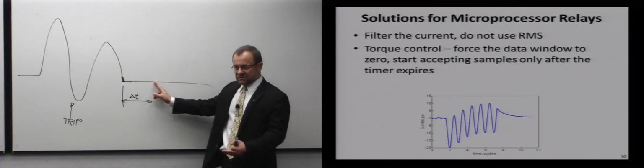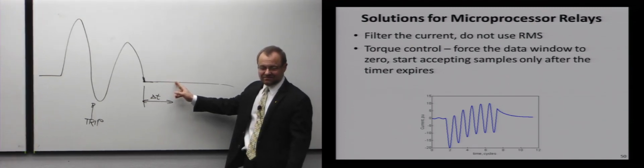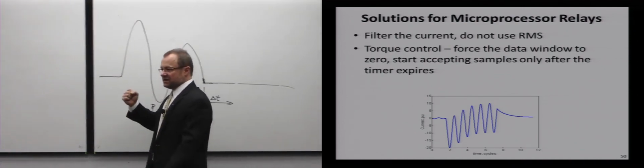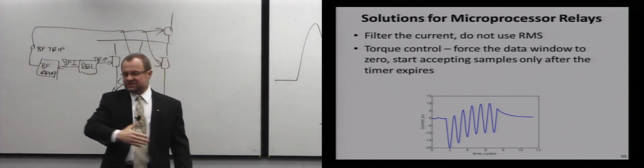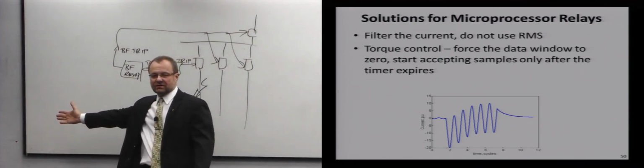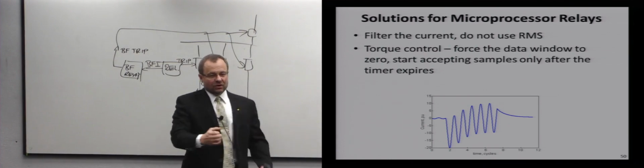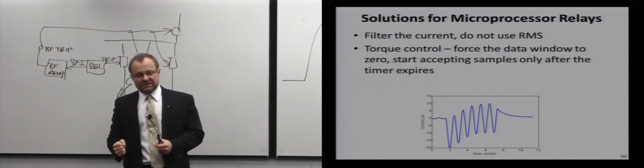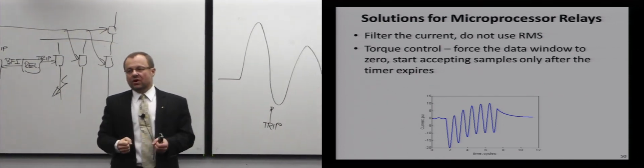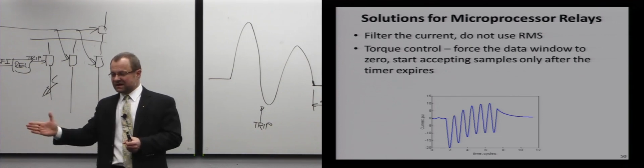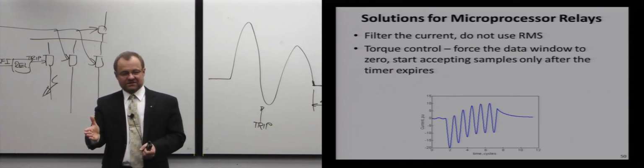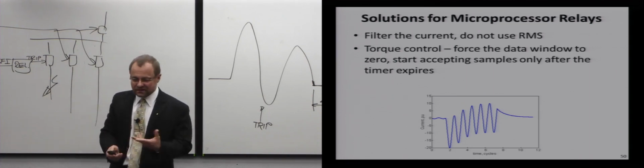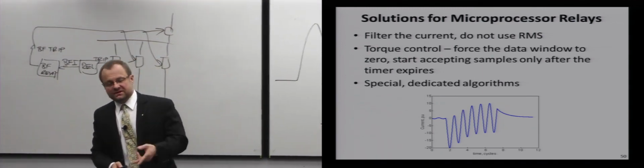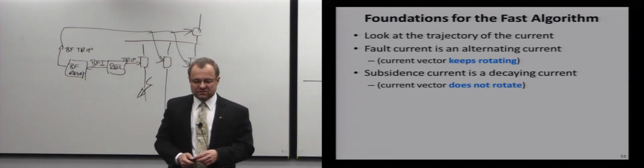So when my timer expired, say up to here, I start running that estimator and I say take a sample and see and run it through a Fourier. So if the current is gone, I will fill my window with zeros and the output I'm getting is zeros, right? So I will not let that kick coming from the fault move my measurement instrument all the way to 20 and then complain that it takes so long to go back with the needle to 0, right? I will hold my instrument, don't let it go to 20, and when the timer expires and the system tells me, now go and check if there is a current, I will release the needle of my ammeter, and if the current is gone, it will stay at 0, right? So a smarter approach. But we could think of a special dedicated algorithm. So this is one of them.